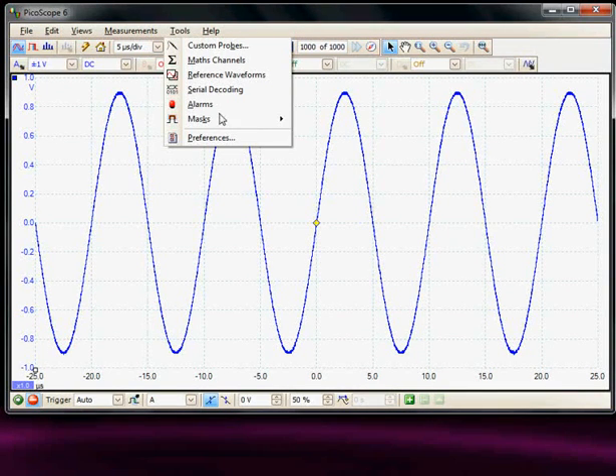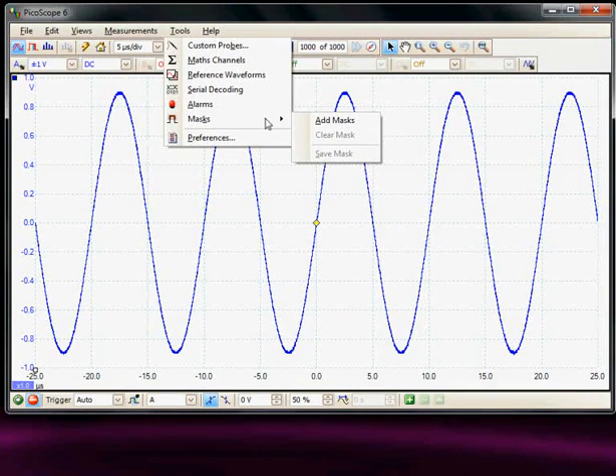And the mask menu is below that, so here we can build our own mask around a waveform and then use the alarm to check it.